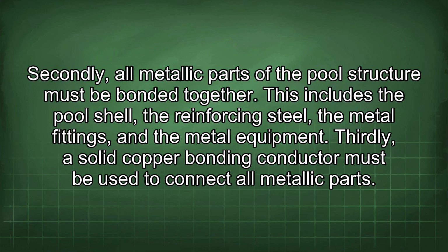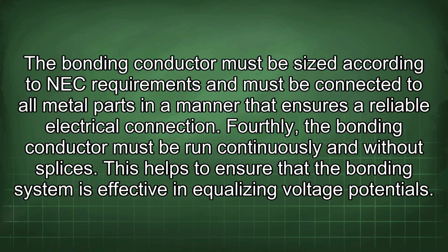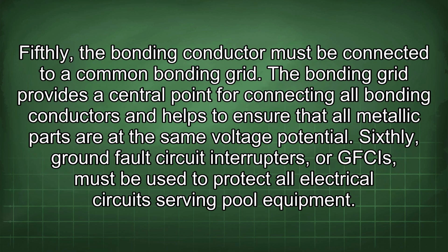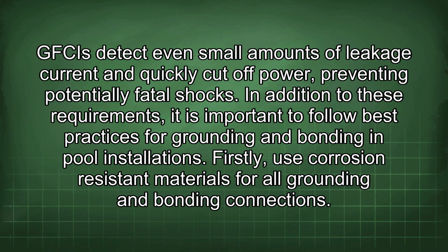Thirdly, a solid copper bonding conductor must be used to connect all metallic parts. The bonding conductor must be sized according to NEC requirements and must be connected to all metal parts in a manner that ensures a reliable electrical connection. Fourthly, the bonding conductor must be run continuously and without splices. This helps to ensure that the bonding system is effective in equalizing voltage potentials. Fifthly, the bonding conductor must be connected to a common bonding grid. The bonding grid provides the central point for connecting all bonding conductors and helps to ensure that all metallic parts are at the same voltage potential. Sixthly, ground fault circuit interrupters, or GFCIs, must be used to protect all electrical circuits serving pool equipment. GFCIs detect even small amounts of leakage current and quickly cut off power, preventing potentially fatal shocks.